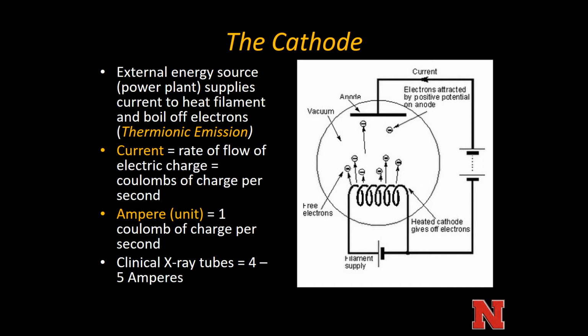Usually, like in a CT, for example, you set the parameters for the current that's going to be used to expose a patient to X-rays, and usually that's in milliamps, something like 10 to 500 milliamps at maximum. A lot of CTs actually automatically adjust the current utilized to expose the patient based off of their size or thickness, etc., with automated limits so a patient isn't burned. But the amount of amperage or current that it takes to actually run an X-ray tube is measured in amps, not milliamps.